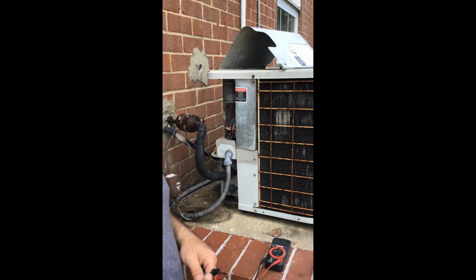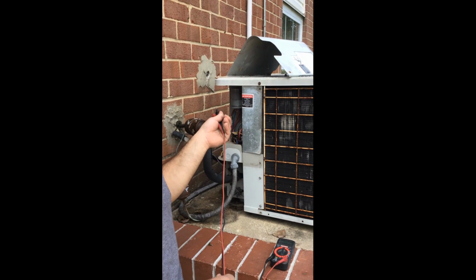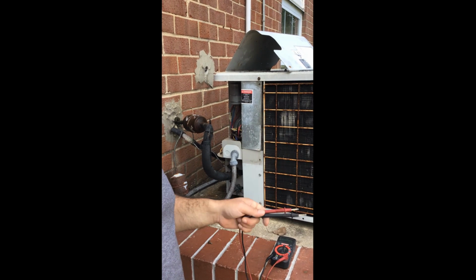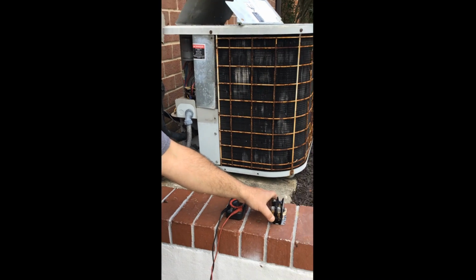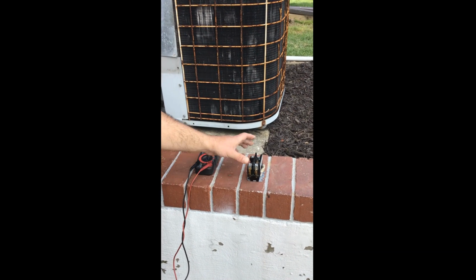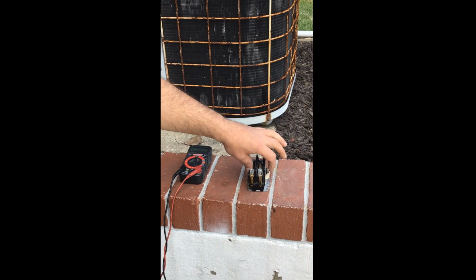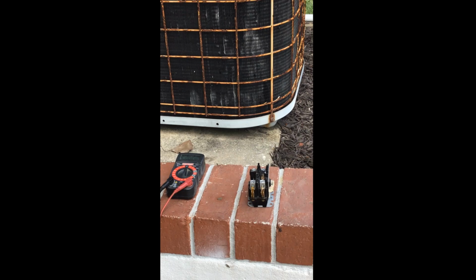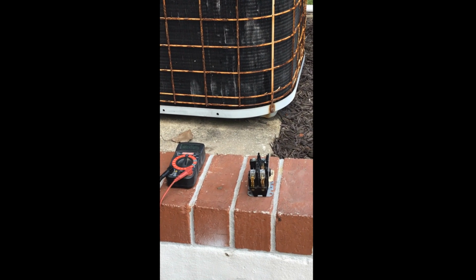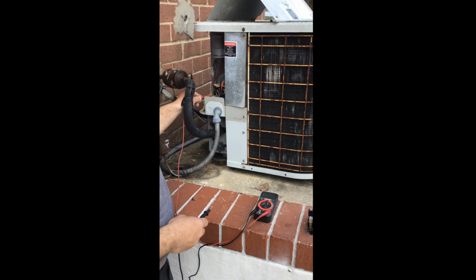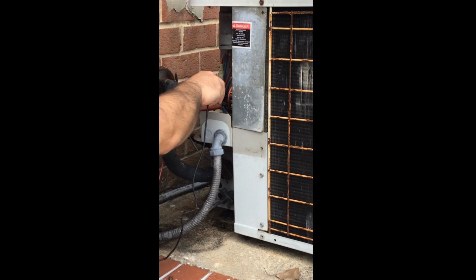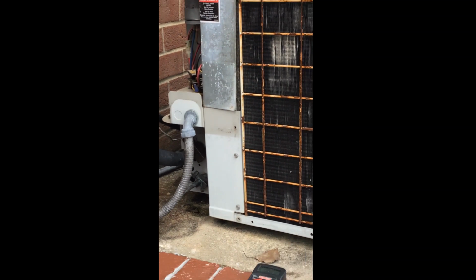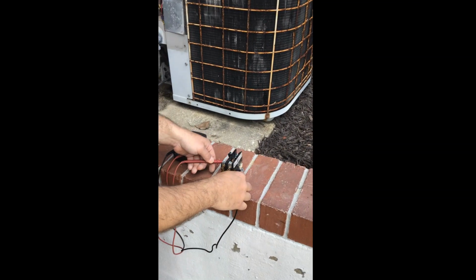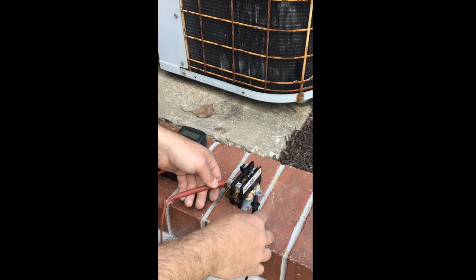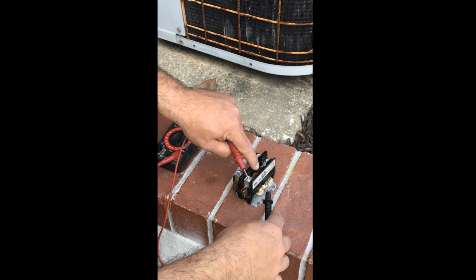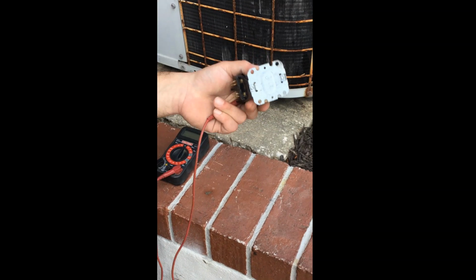Okay, so we're back outside and we're going to wrap up with talking about the last component in the 24 volt circuit. And ironically, that's the very first thing we talked about, your AC contactor. We talked about this first because it has 240 going through it, and it also has 24 going to each side. So after we perform all the checks we performed inside and everything turns out right, you come outside to measure on your 24 volt terminals, and you have 24 volts. It'll be easier to see here. Come outside, you have 24 volts across, but this is not pulling in. You know your contactor's bad.